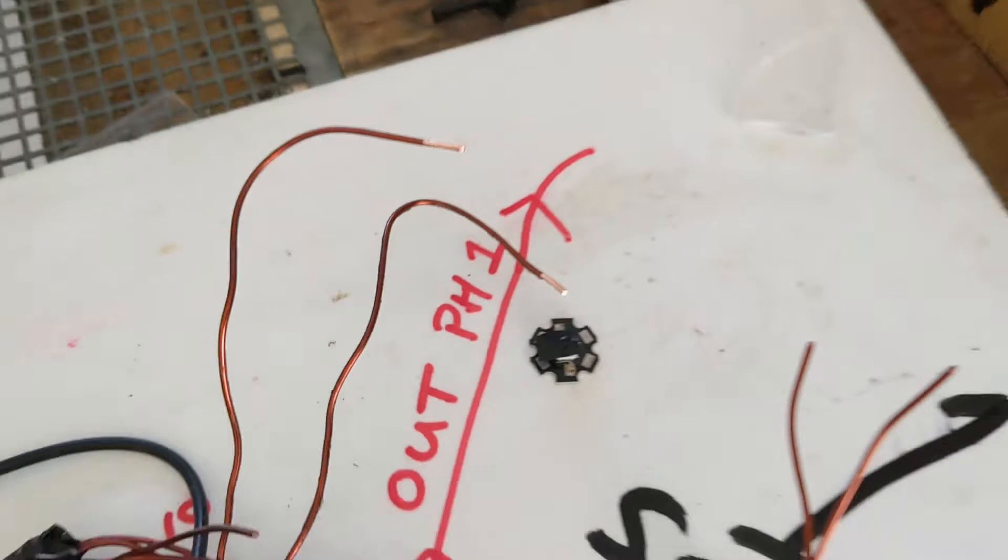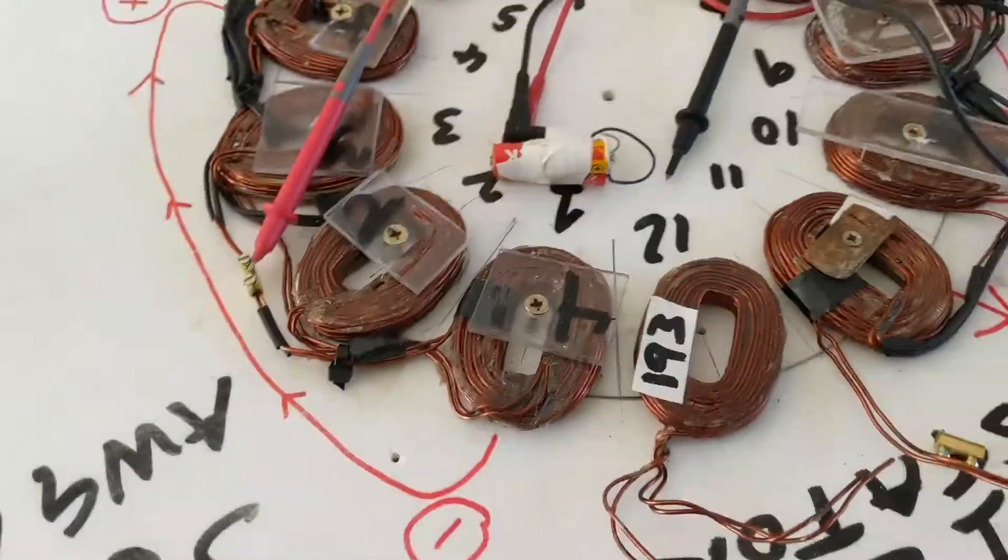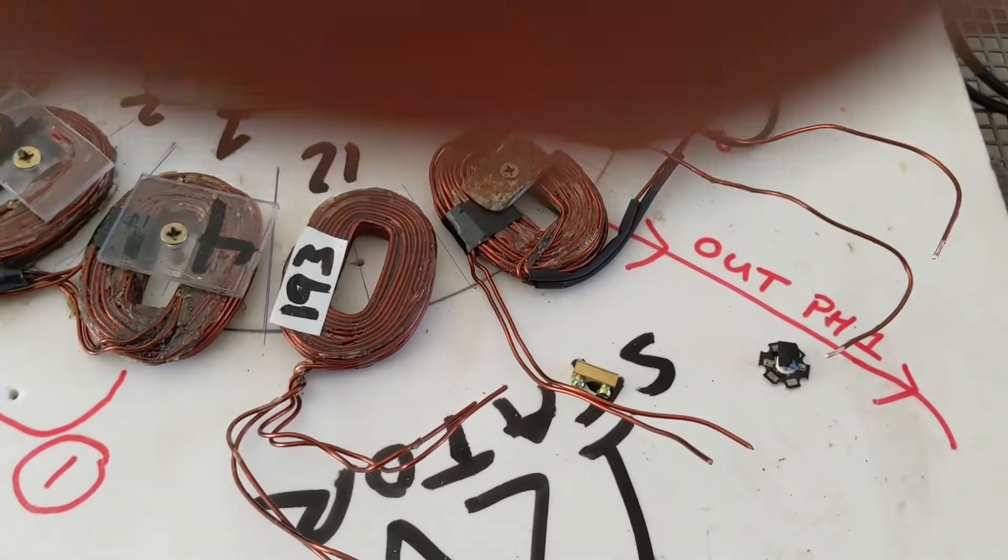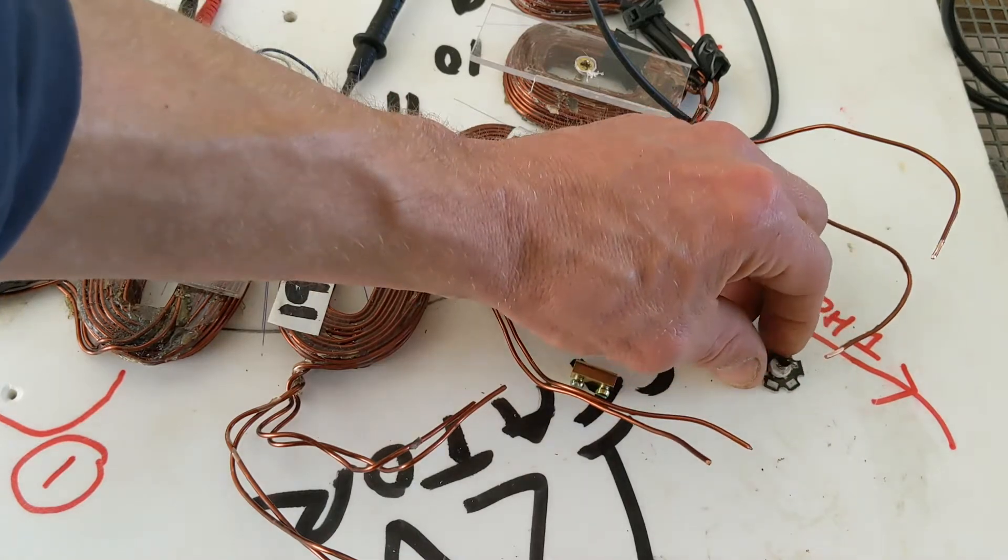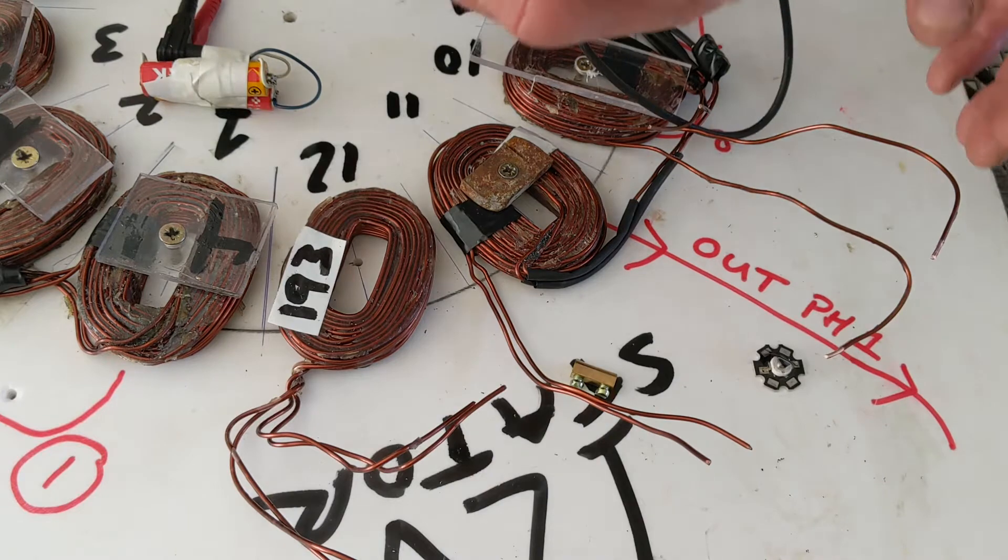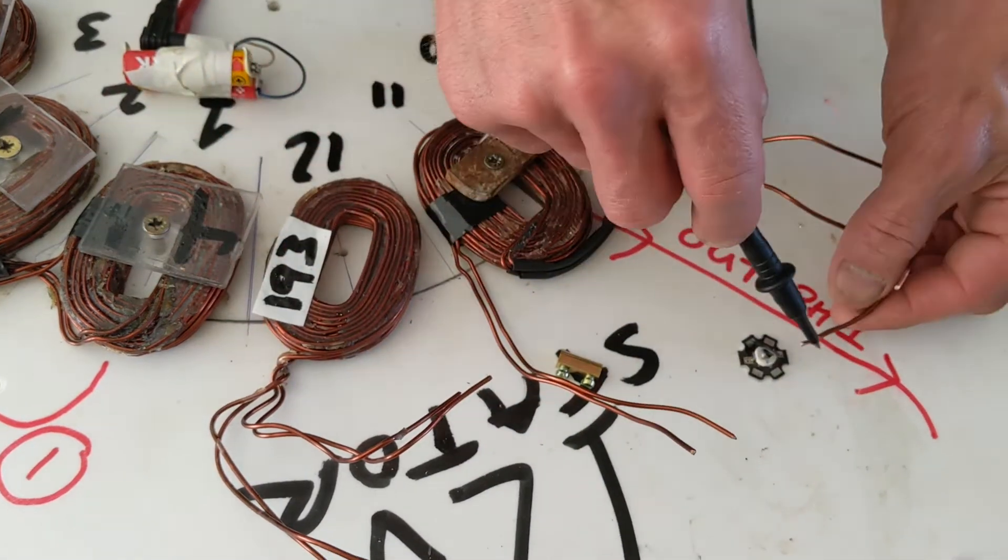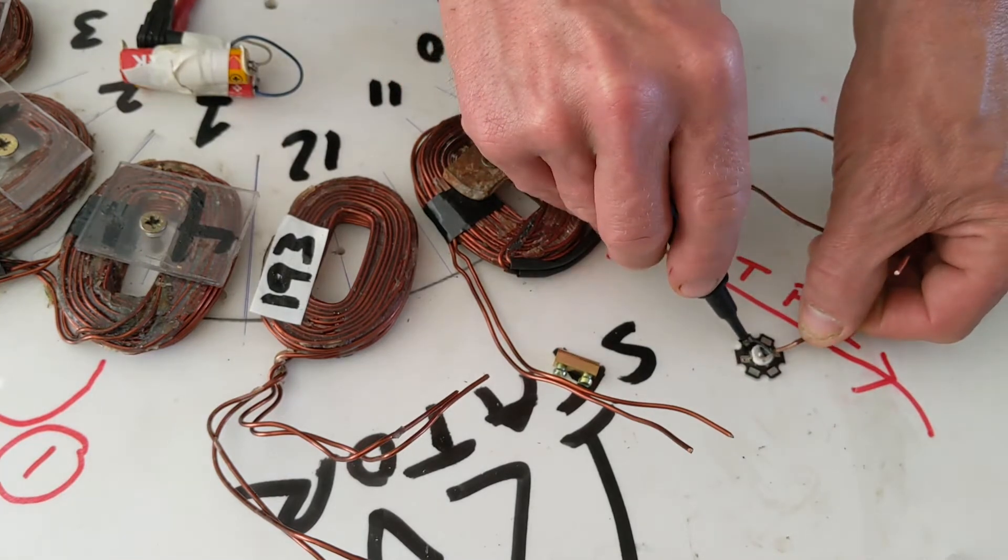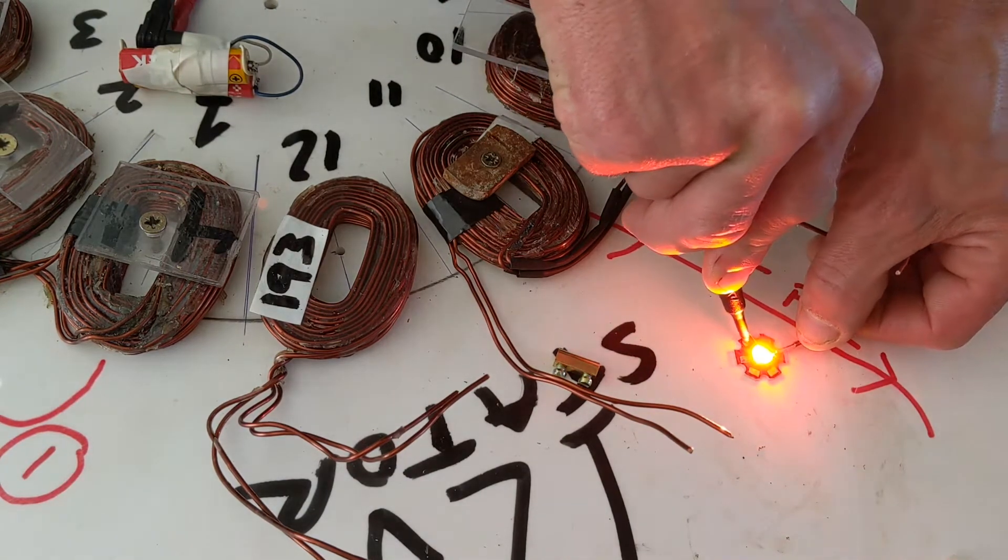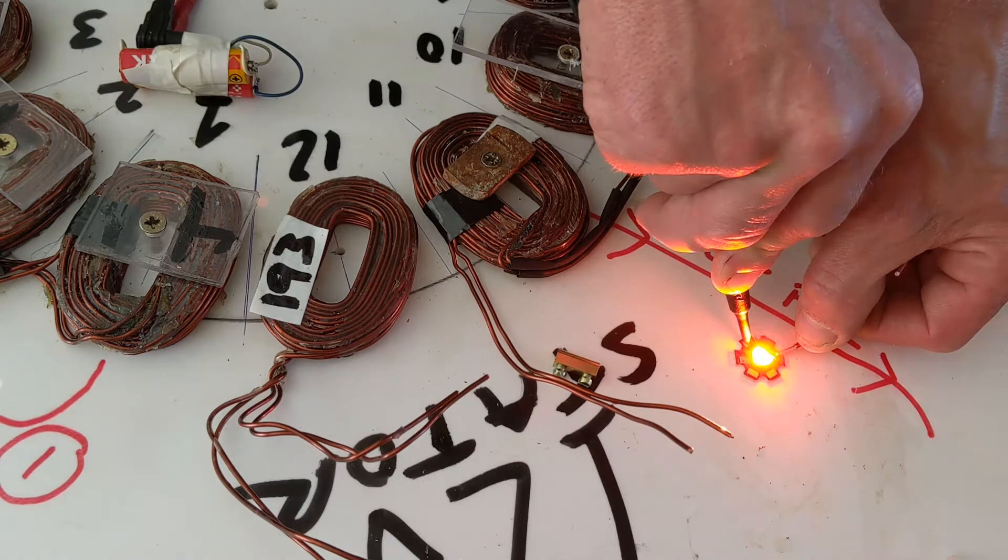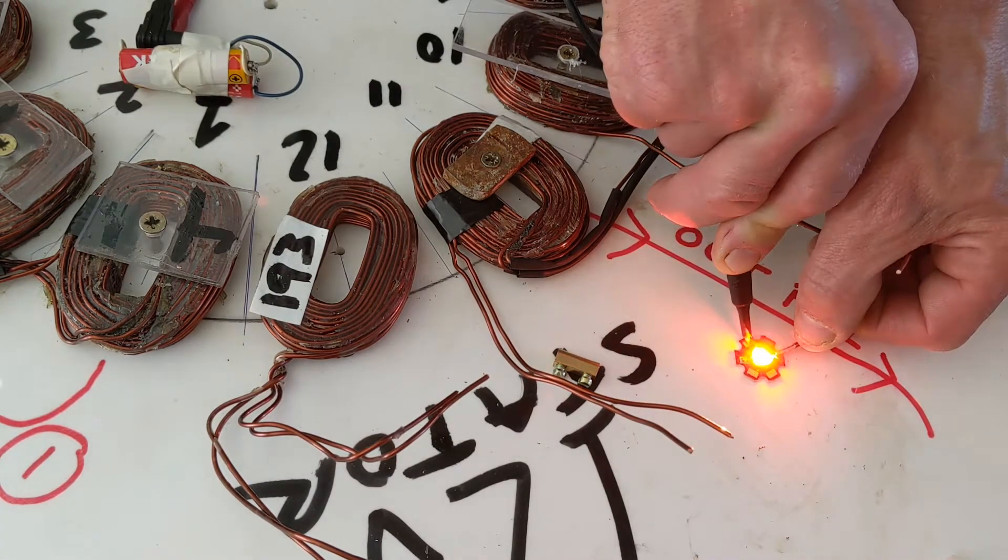So I'm just going to show you how you can check that continuity using the batteries and an LED. I've got a bit of tape on the LED because of how bright they are. So I'll just show you how it should work. When I put this on the negative of the LED and then this on the positive it should come on. There you go. So that shows that power can run through, is running through from coil 1 to 4 to 7 to 10, so that's good.